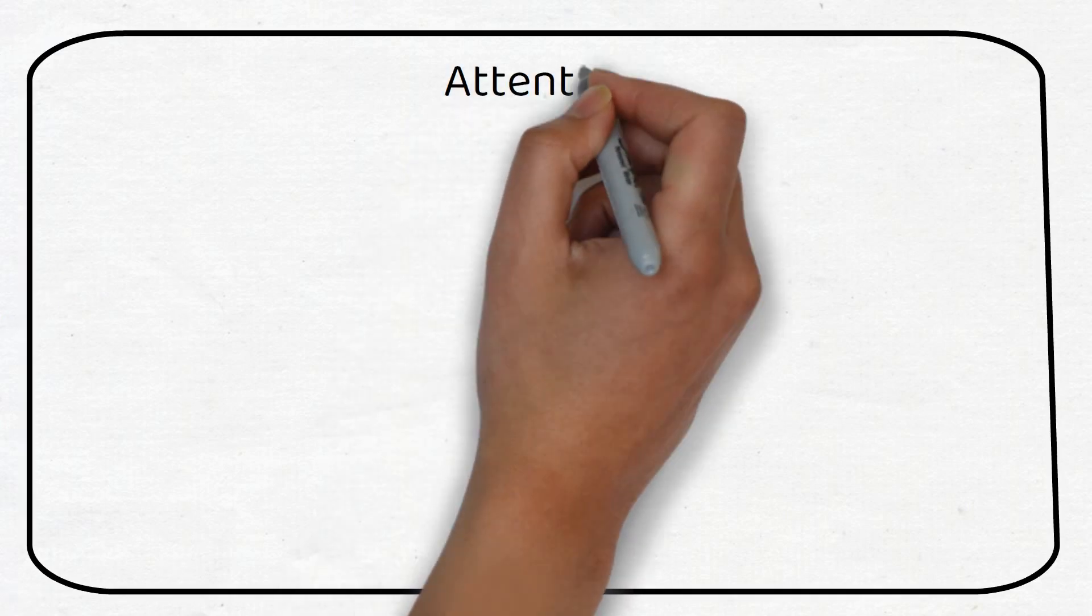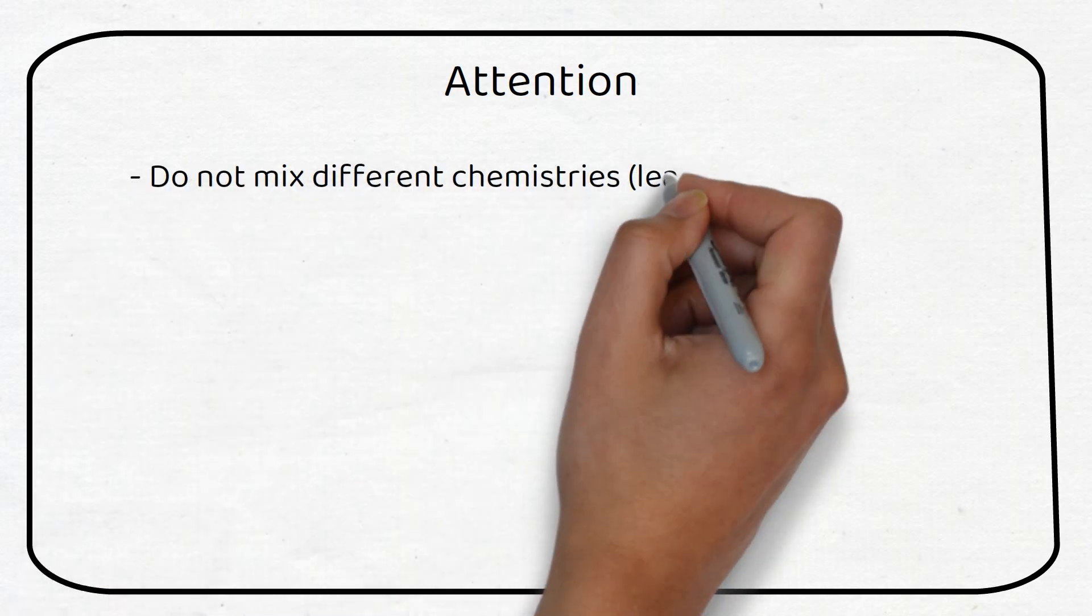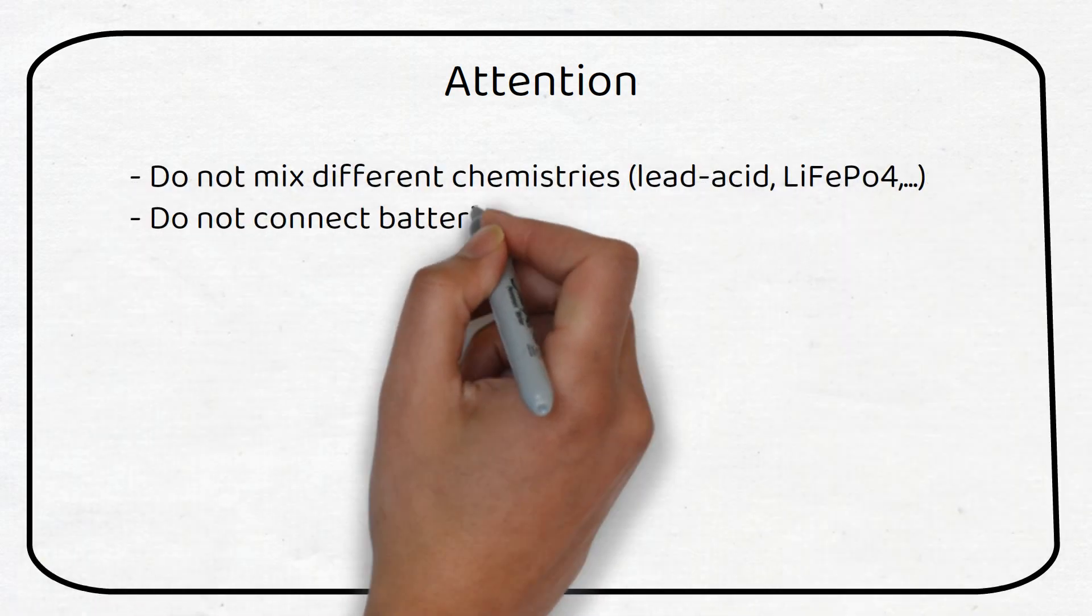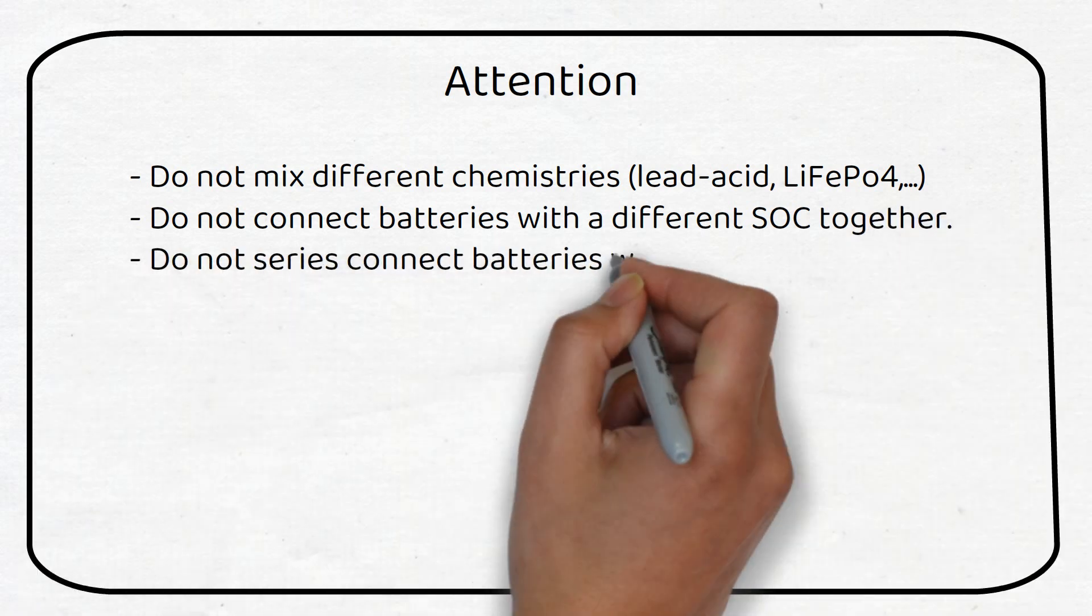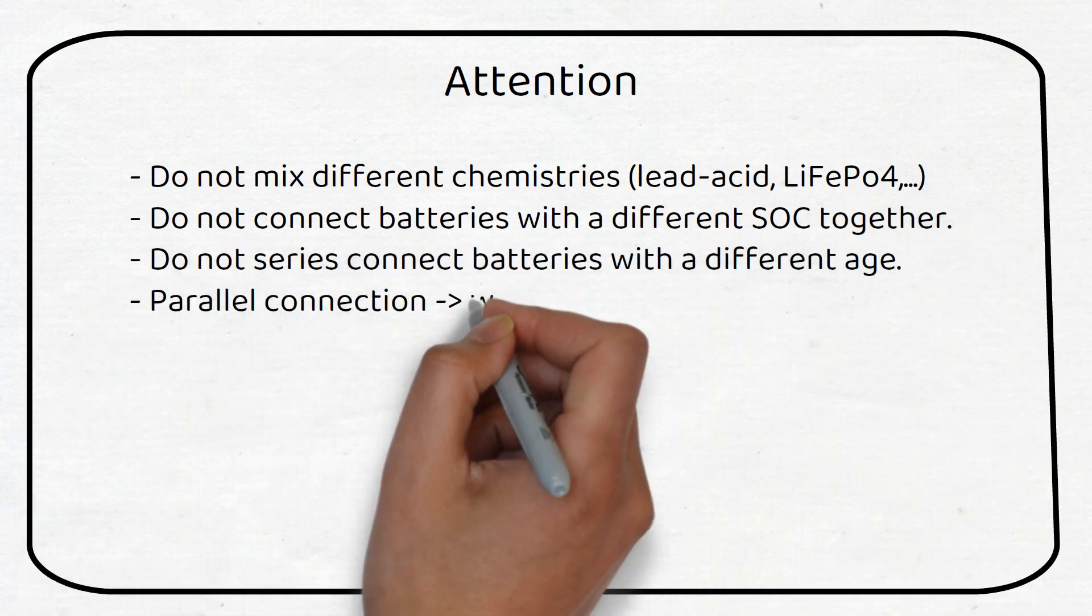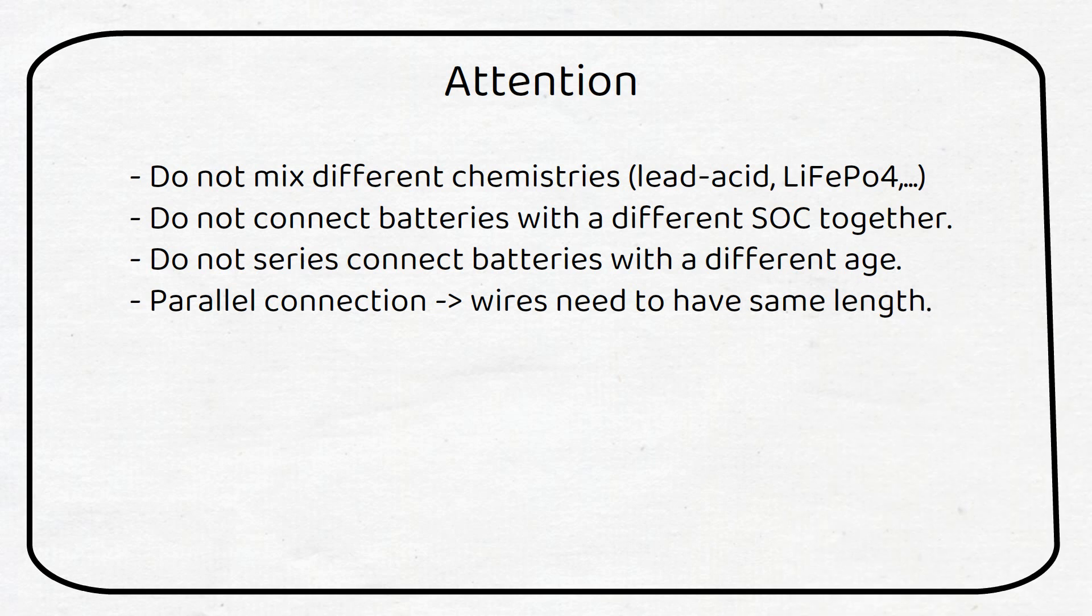There are a few items we need to take into consideration when wiring our batteries together. The first one is to not mix batteries of different chemistries. Another one is to not connect batteries with a different state of charge. The inrush current will be bad for the battery. Instead bring them to the same voltage first and then connect them. Do not series connect batteries with a different age. The capacity of these will be reduced and reduce the total capacity of your battery.